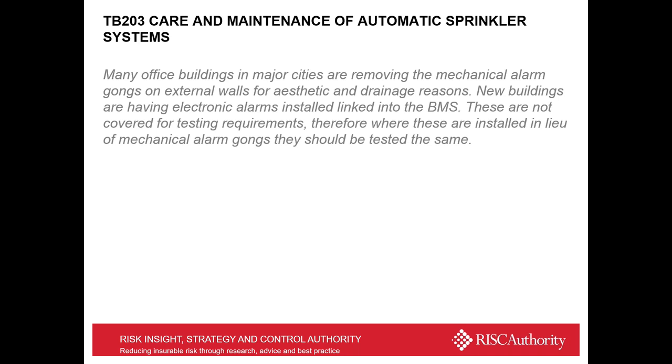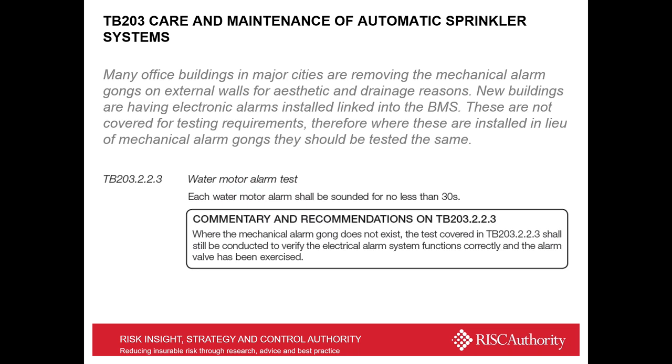So fire alarm systems are now incorporating electronic alarms in lieu of mechanical alarm gongs. And where this is done in London or Birmingham or Manchester in the office blocks, it's just confirmation in TB203 that it should be tested on a weekly basis. So it's pretty straightforward. Where no mechanical alarm has been fitted and an electronic alarm has been installed in lieu of the mechanical alarm gong, weekly testing should be covered for an electrical alarm as well as there is for a water motor alarm gong.